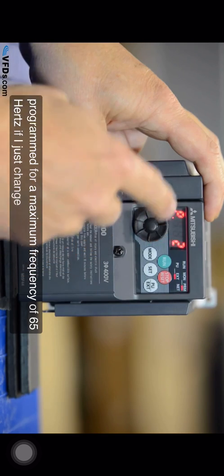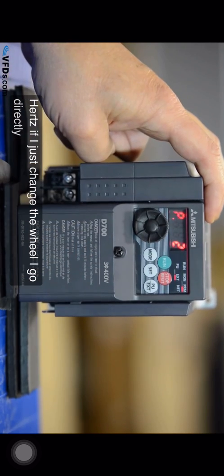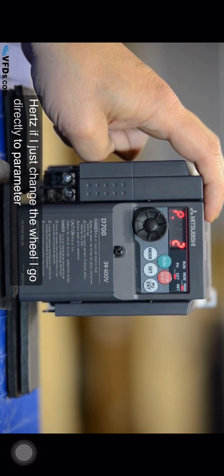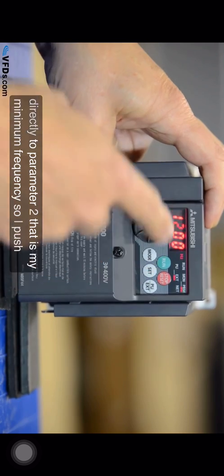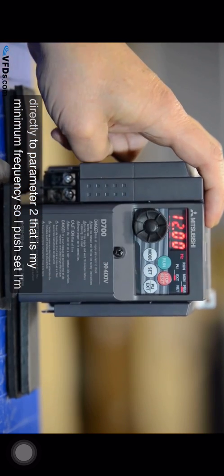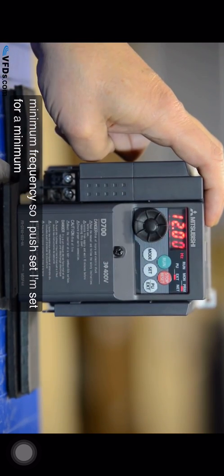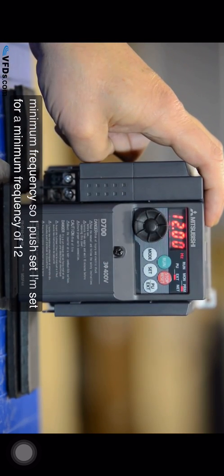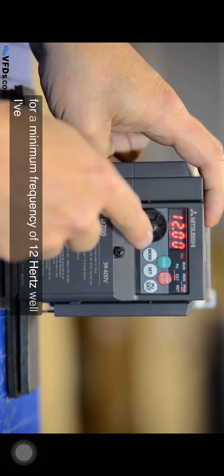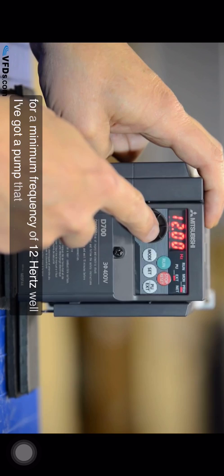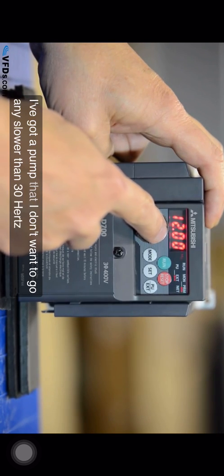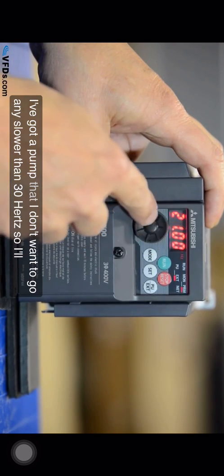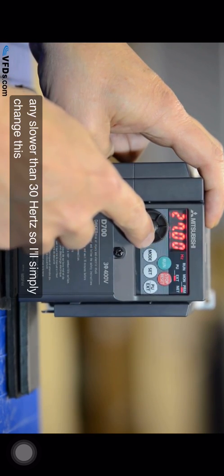If I just change the wheel I go directly to parameter two. That is my minimum frequency. So I push set. I'm set for a minimum frequency of 12 hertz. Well I've got a pump that I don't want to go any slower than 30 hertz so I'll simply change this.